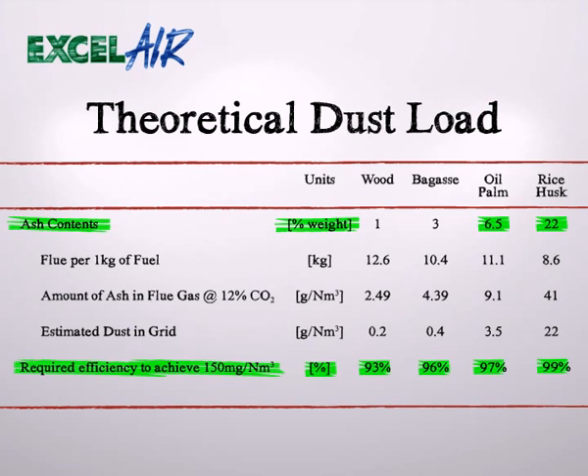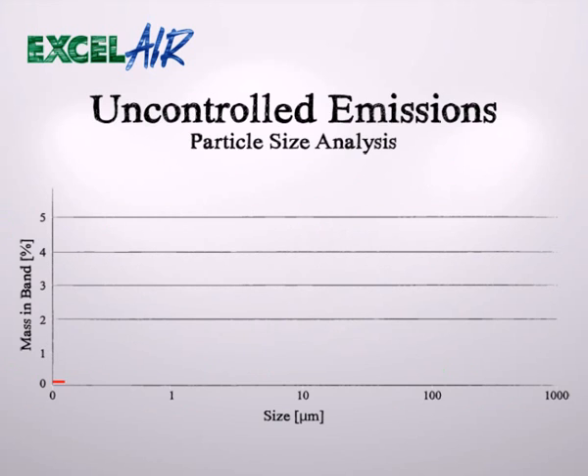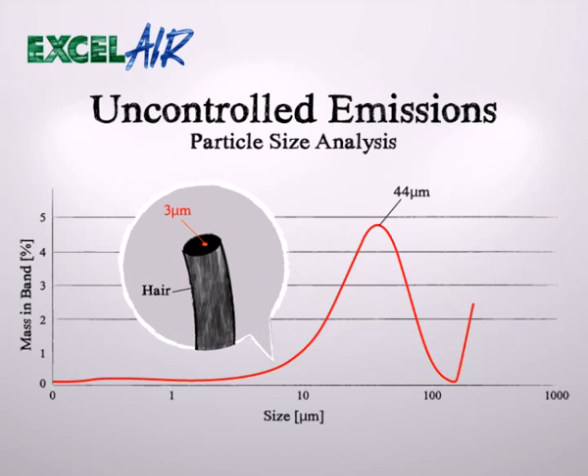From this chart, it is evident that fuel from typical biomass may influence the dust concentration by a factor of 10. While the ash content varies considerably, the particle size distribution after a properly operated boiler is remarkably consistent. A typical distribution is shown in this graph. To keep the particle sizes in perspective, a typical human hair is 70 microns in diameter, and the dot on the hair is 3 microns.